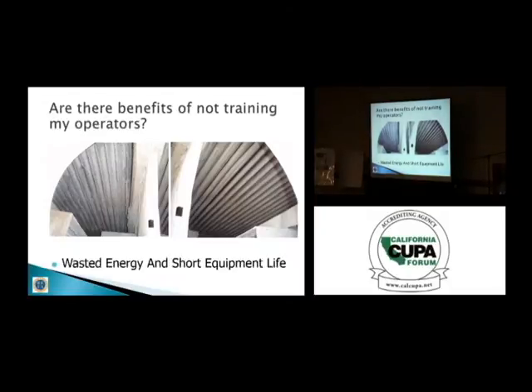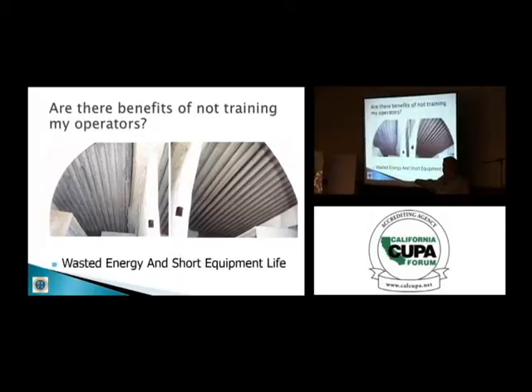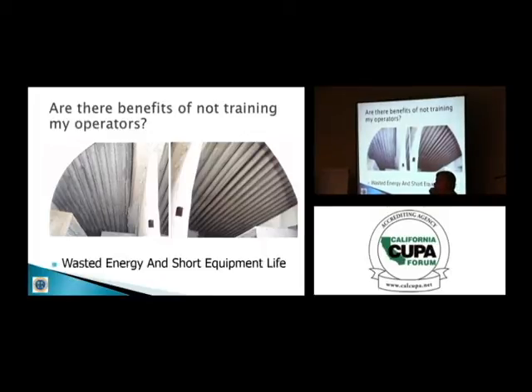Remember that device, the condenser, that's to reject the heat energy? The more you impede that transfer of heat, the higher the pressure is going to be. The higher the pressure, the more you have to pay in power to reject that heat, because it's a difference of your inlet pressure of your compressor and its discharge. And if you turn your heat exchange surfaces into a coral reef, that's a good insulating jacket.